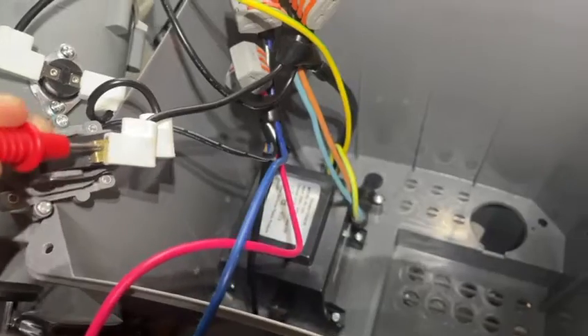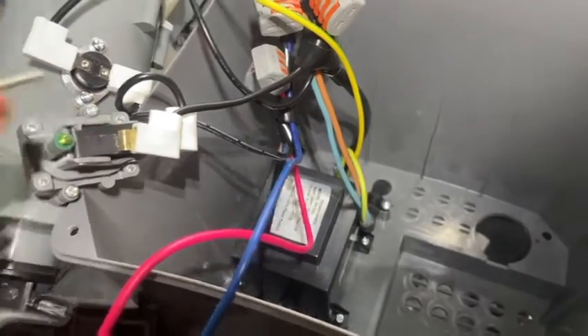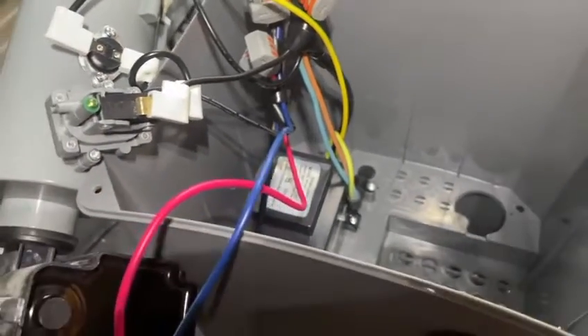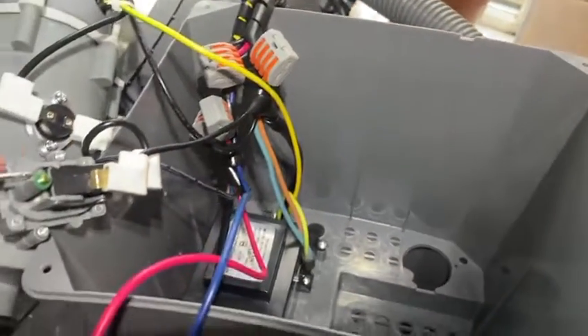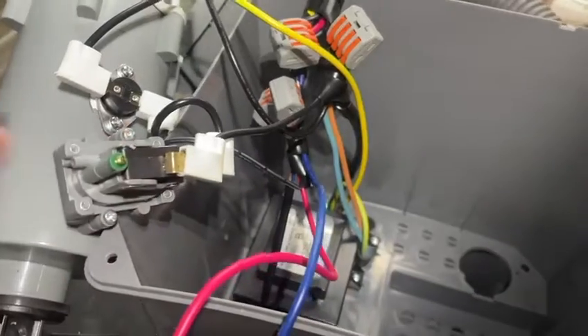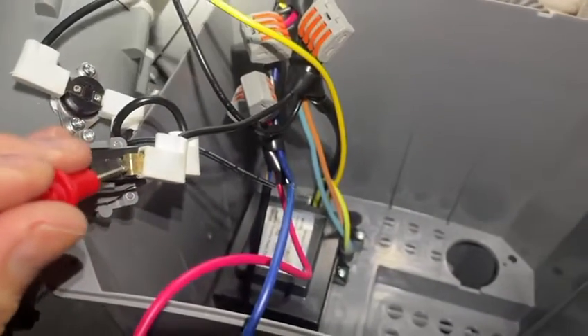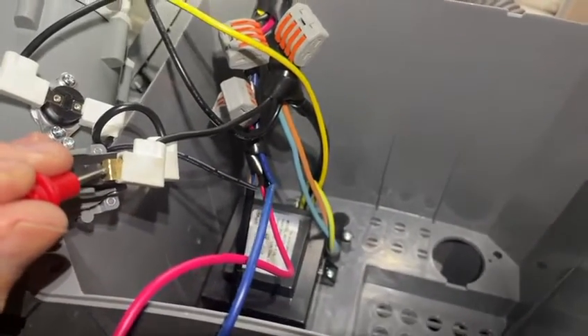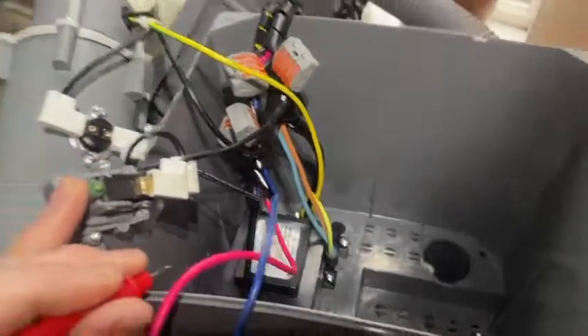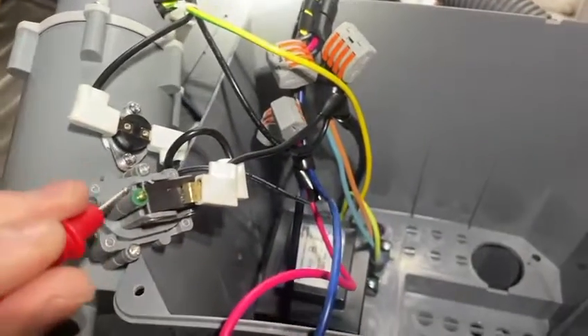But what you can do is when you've filled it with water - obviously don't switch anything on, don't put any power through the unit because you don't need to - when you fill it with water and test for continuity, when there's water in here you should be getting a signal of continuity through these two terminals. If you're not, then this is obviously faulty.